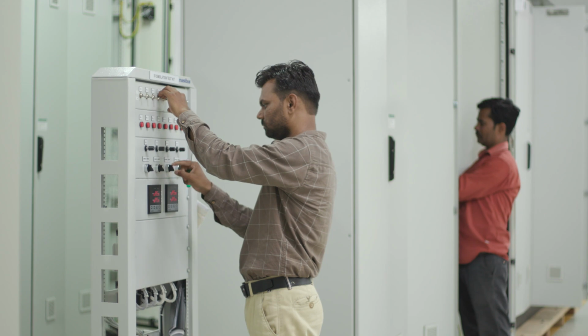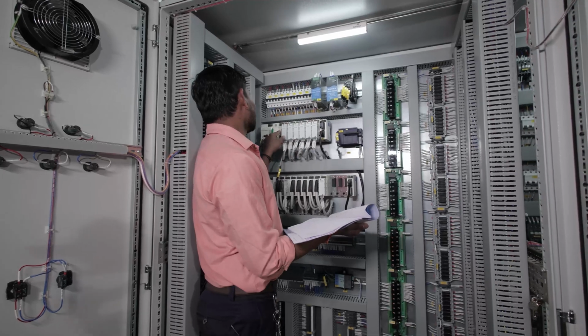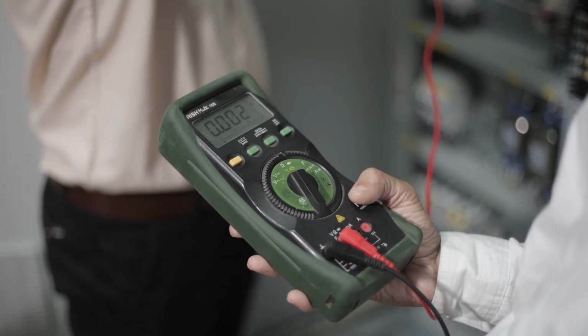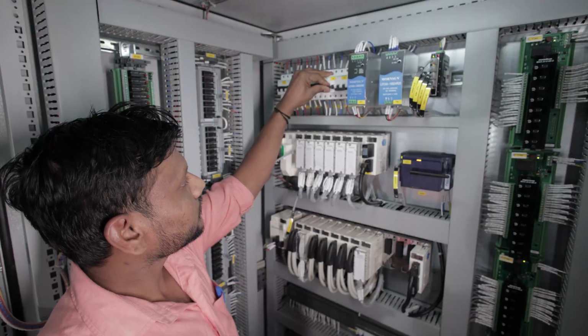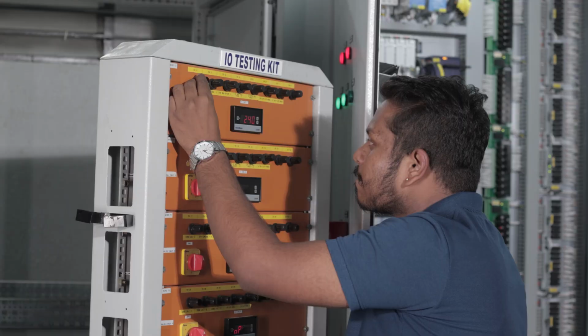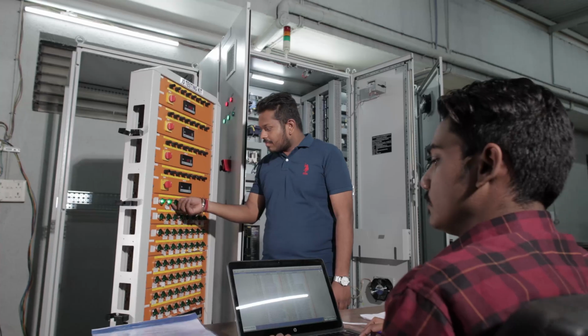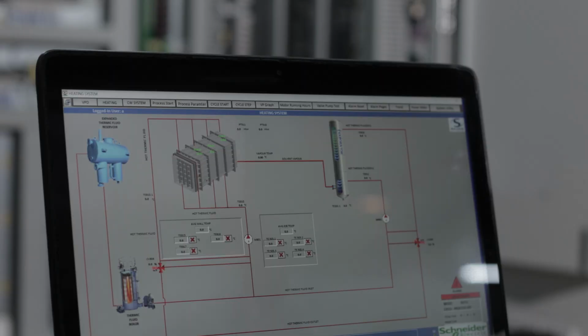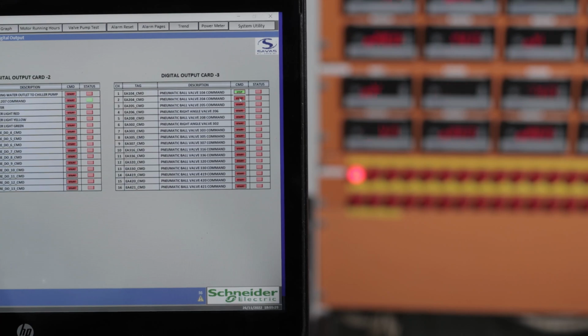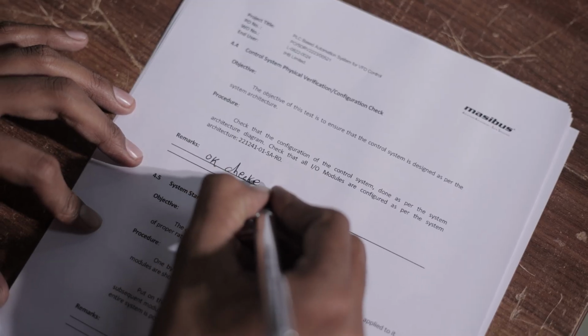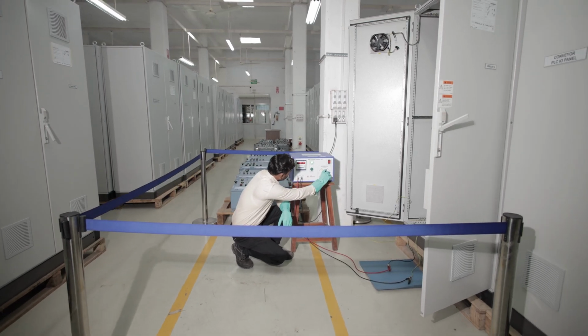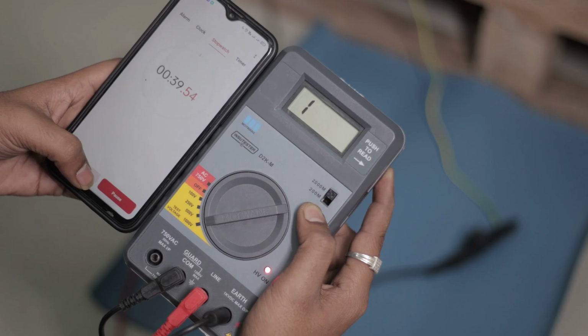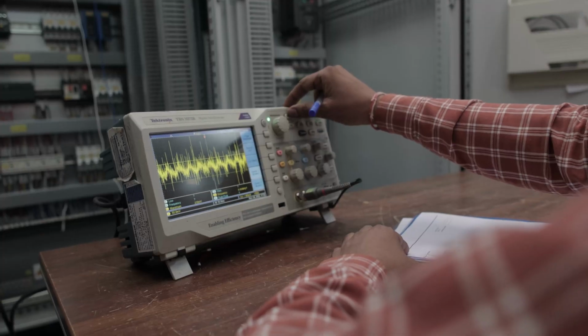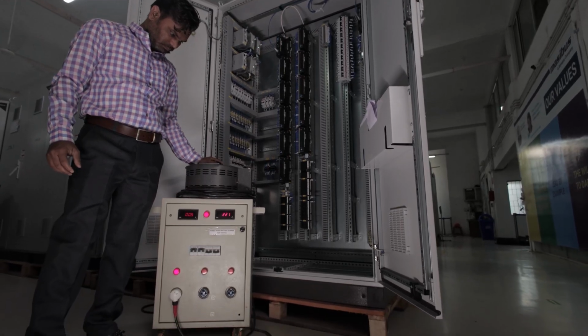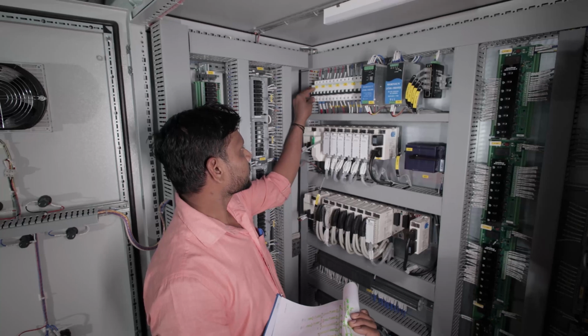Our team conducts internal FAT for various tests like continuity check, power-on test of individual electrical components, input-output simulation using automated test jig, logic simulation test, SCADA simulation test, and finally generates an internal FAT report. Some special tests like high voltage test, insulation resistance test, ripple test, power fluctuation test are also performed based on the project requirement.